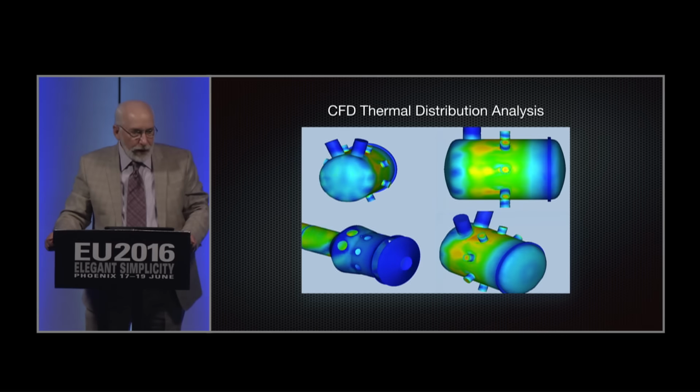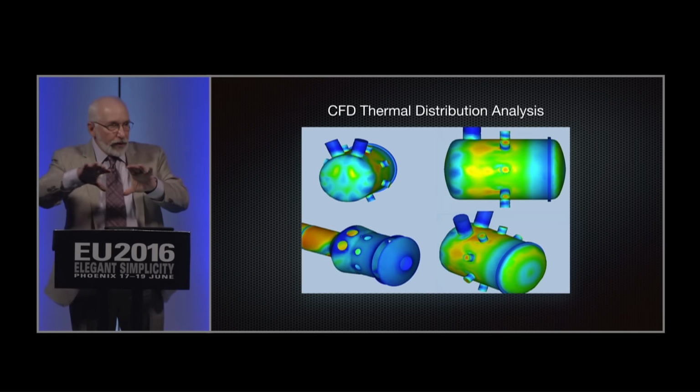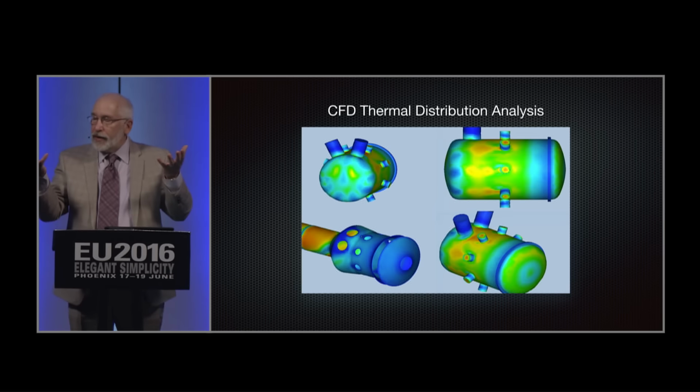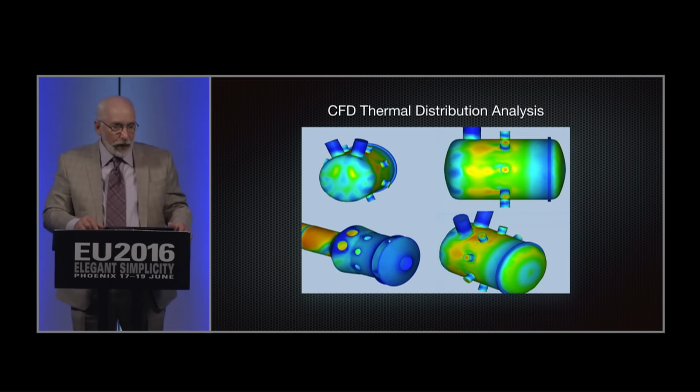And this is some of the thermal distribution, and it's a lot more even. So we're not getting 500 degrees now. If I can get a fan to pull air over the surface, we can bring the chamber into stability at around 100 degrees Celsius. Now that's something we can work with. It's still going to boil water, but the worst case scenario is about 100 degrees Celsius. It's not going to melt gaskets. Yes, you could fry eggs on it, but it's workable.